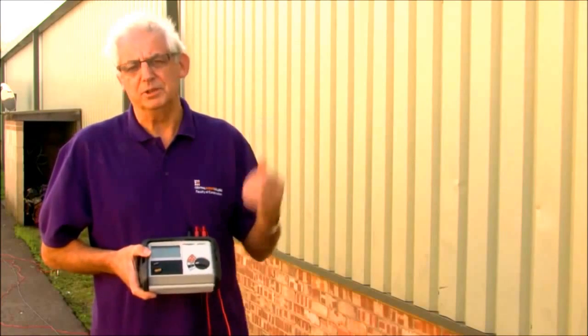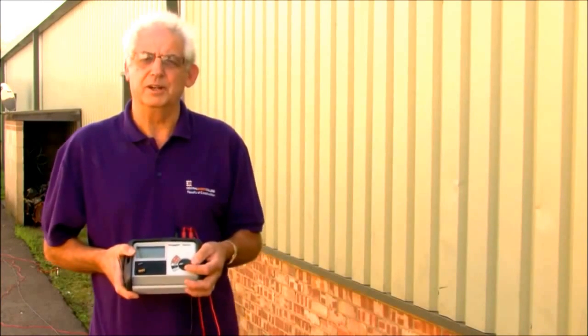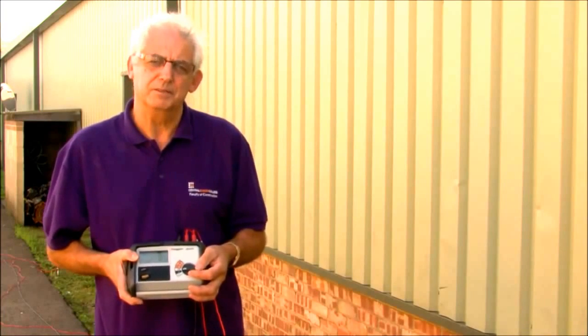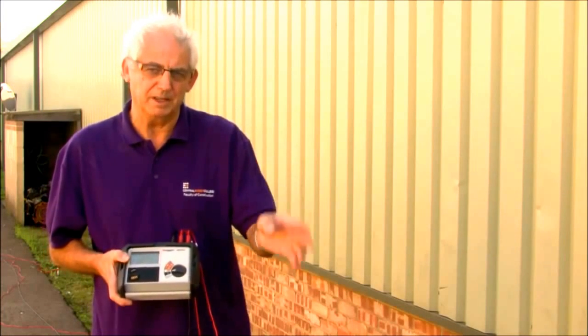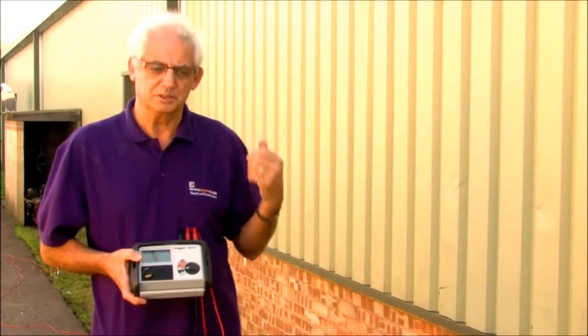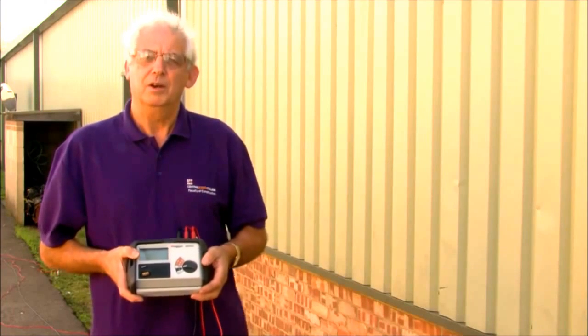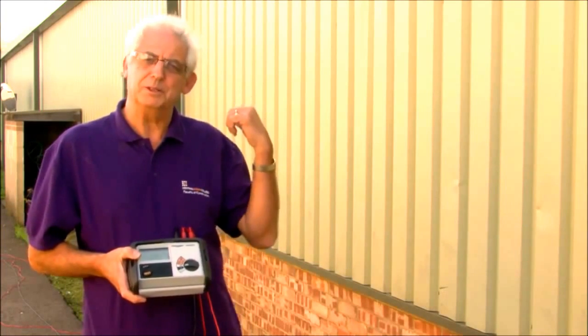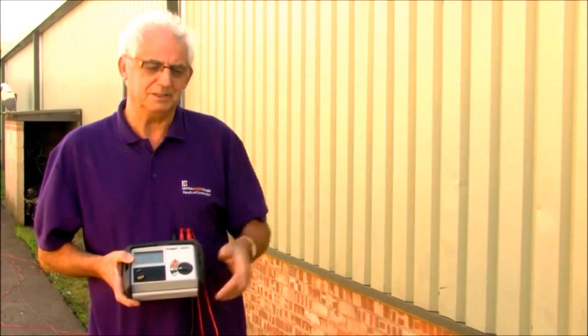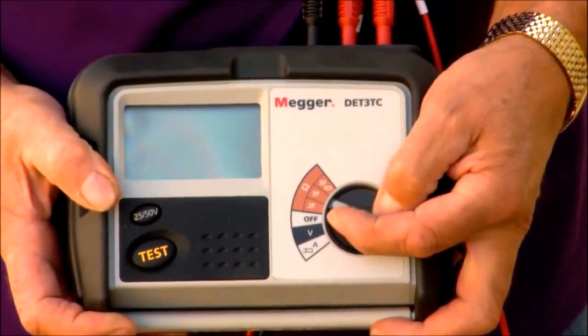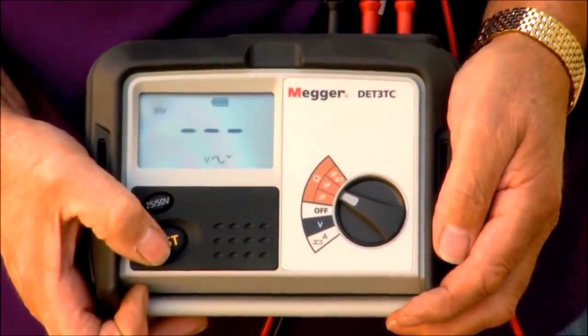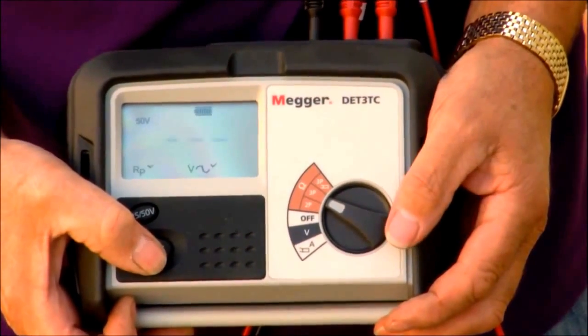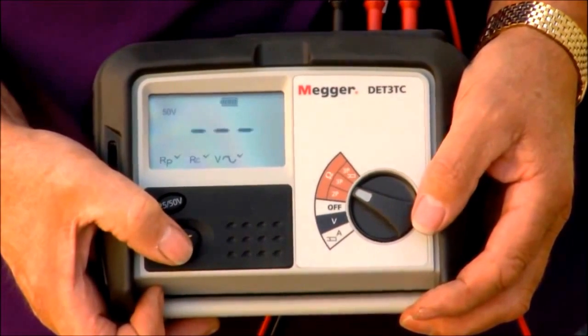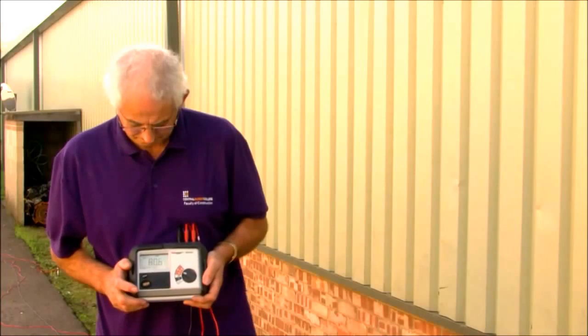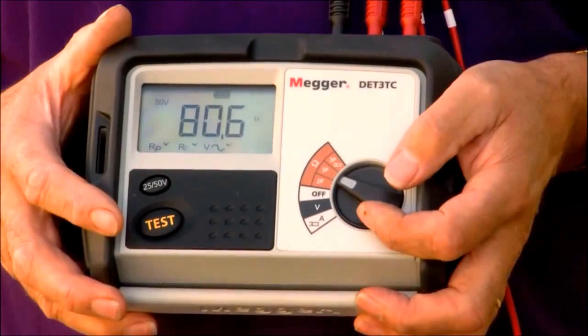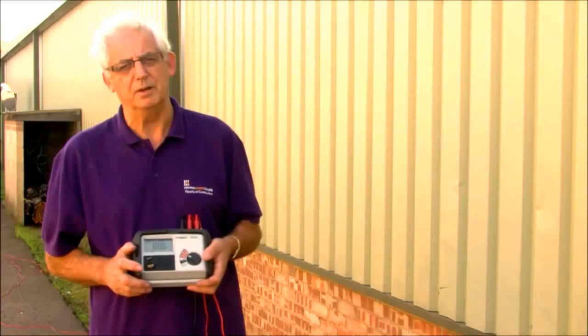I've now moved the potential electrode closer to the electrode under test. It needs to be 10% of the total distance between the electrode under test and the current electrode. So as that was 2 meters deep, and the distance apart was 20 meters, I've moved the electrode 2 meters nearer to the electrode under test. Now I'm going to take another reading. 80.06. The first one was 80.08.